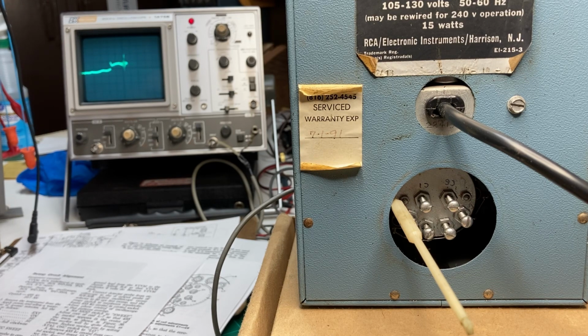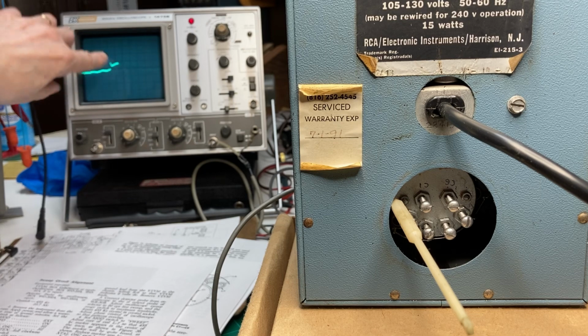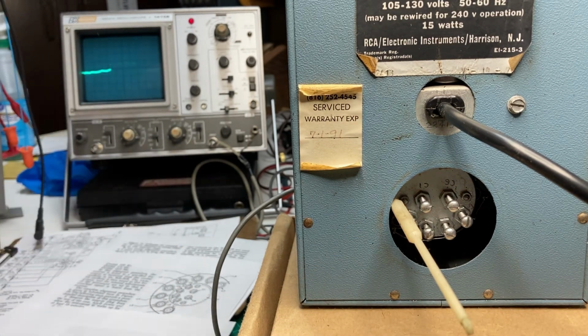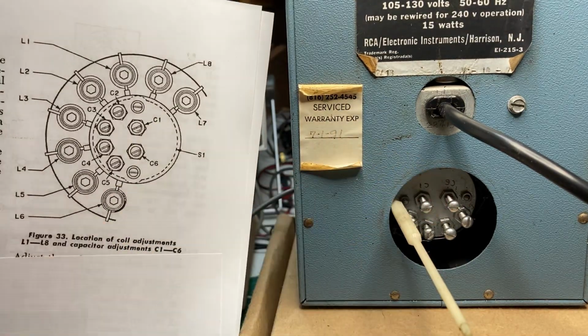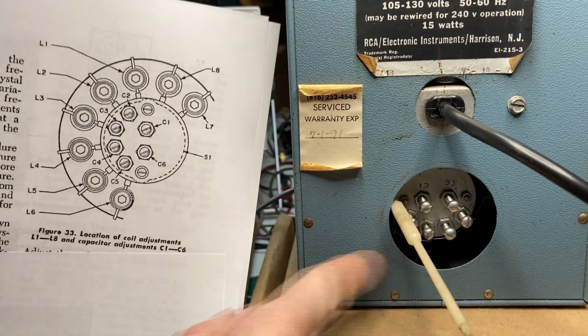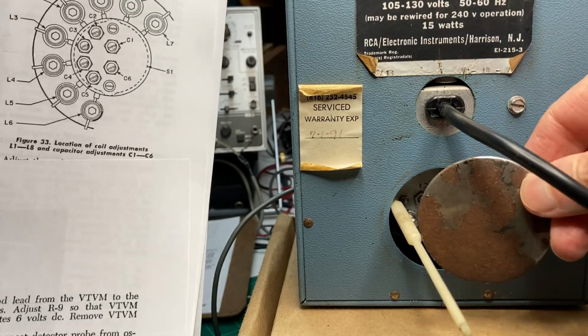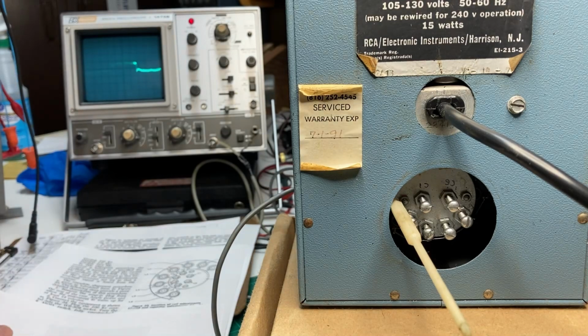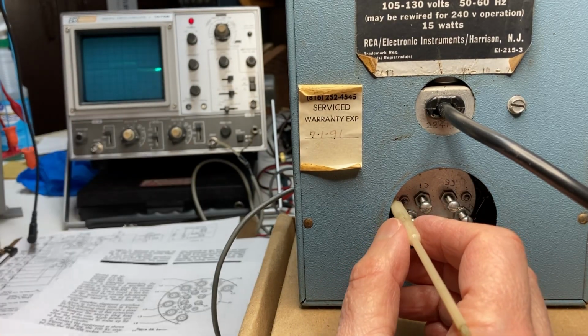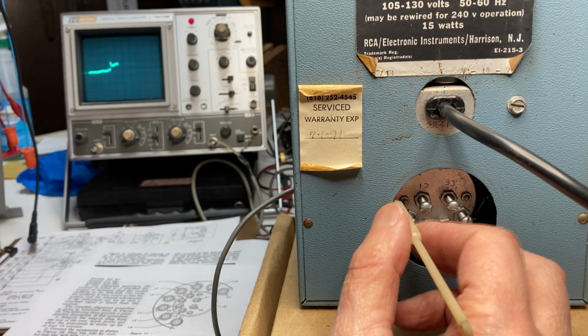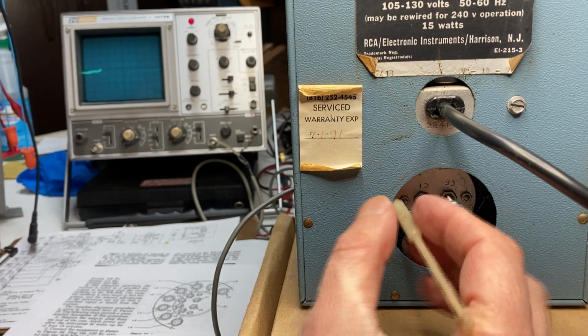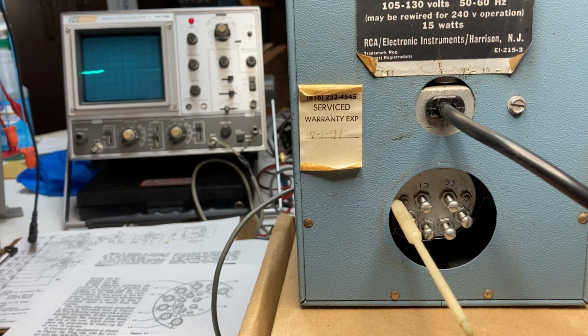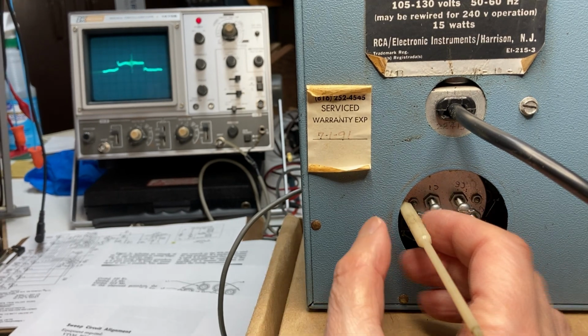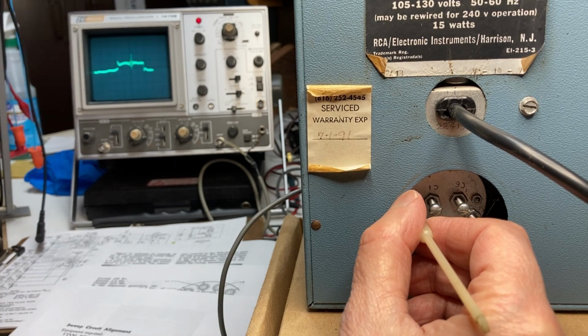Okay, and I also wanted to mention that you can adjust the center mark of the sweep using L7 and L8 inductors in the back of the signal generator. Now they were very nice, and they put a little cutout here and inserted a little knockout so you can get to these while it's in the case, which you want to do. And so I've got my tuning wand into L8 for the FM part of it. And as soon as the sweep comes back around here again, I'll show you how that adjusts that. But you'll want to do this for both the 455 kilohertz range and the 10.7 megahertz range for your FM band. Okay, our sweep is showing up again. So what we're going to do is center up the mark on here by adjusting this.